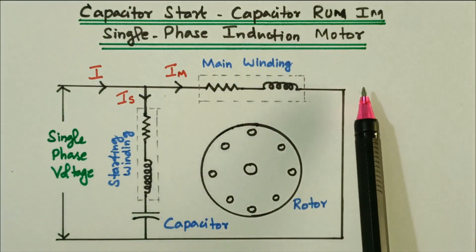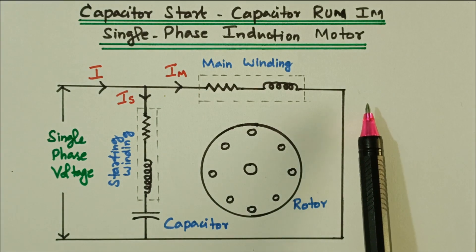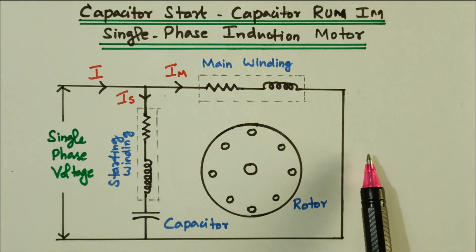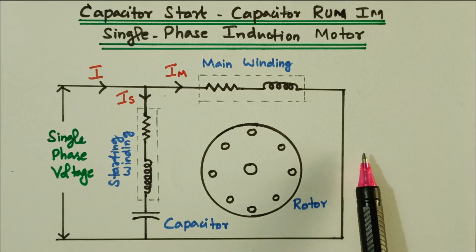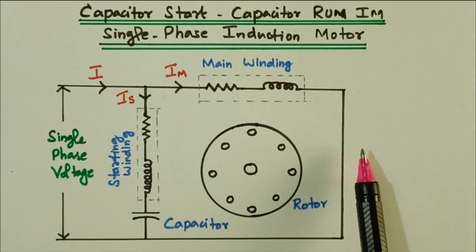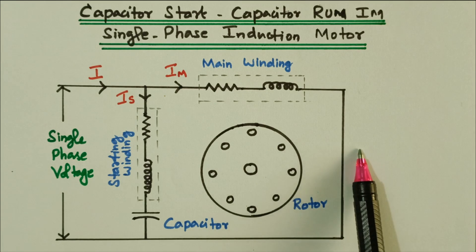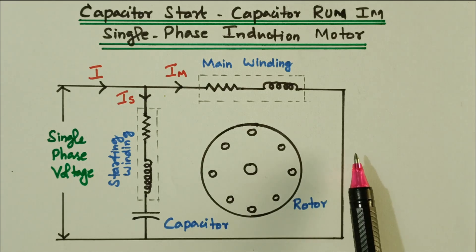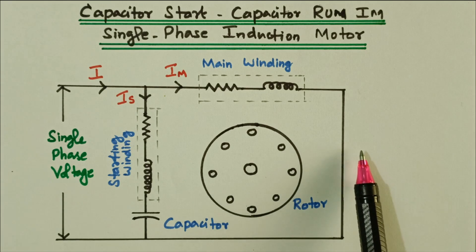We know that a single phase induction motor is not a self-starting motor. In order to make it self-starting, the single phase is converted into two phases. There are two windings and we need to make it two phases. Also, the current flowing through these two phases should have a phase difference — then only the revolving magnetic field will be created.